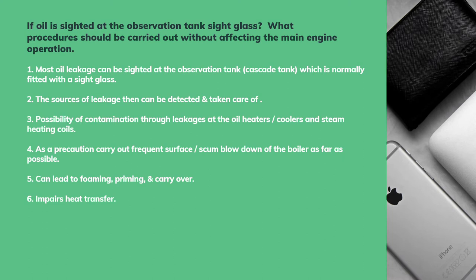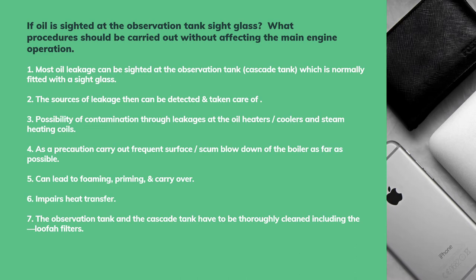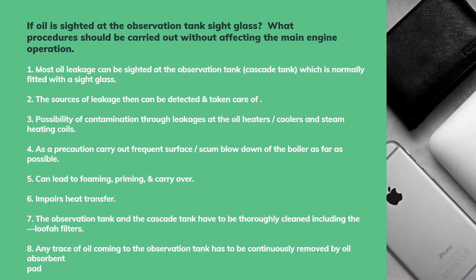Oil impairs heat transfer if there is oil in the hot water system or in the boiler. The observation tank and the cascade tank have to be thoroughly cleaned, including the loofah filter — there is a filter inside that also needs to be cleaned. The tank drain and tank must be cleaned properly. Any traces of oil coming to the observation tank have to be continuously removed by oil-absorbent pads.